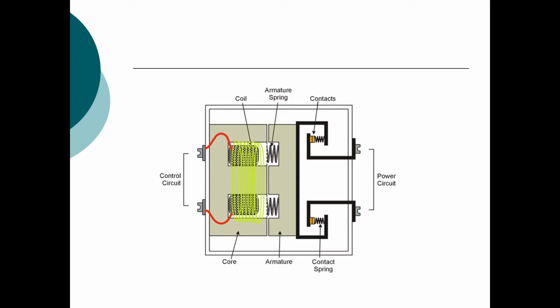The relay also has two different voltage ratings, one for the coil and one for the power circuit. And although they can be the same rating, quite often they are different, and it is important to know what the voltage limitations of your coil and your power circuit are so you do not exceed them.